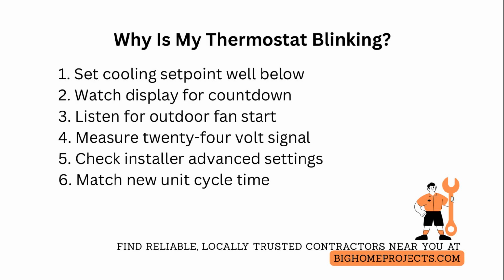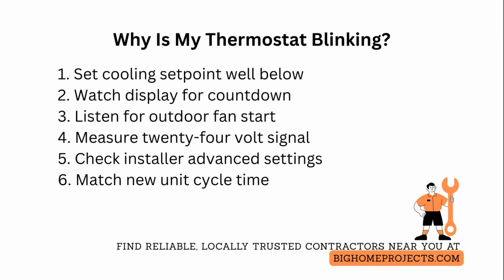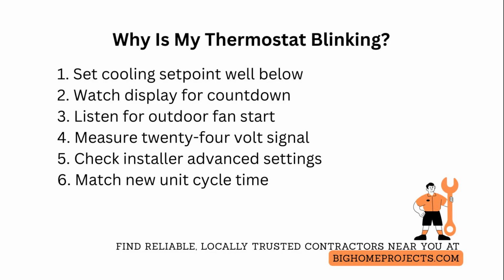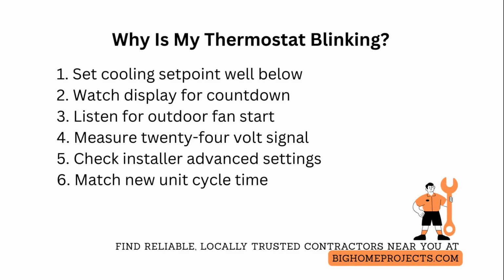If you have a smart thermostat, check the installer or advanced settings for a configurable compressor protection delay and document the current setting before changing it. When replacing thermostats, match the new unit's minimum cycle time and jumper options to the old thermostat, or configure the delay in the installer menu to the recommended factory default to avoid voiding manufacturer warranties.